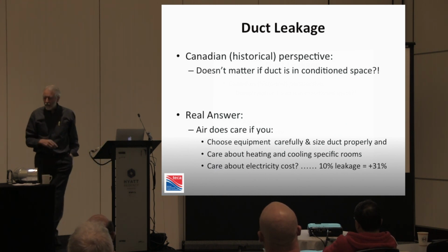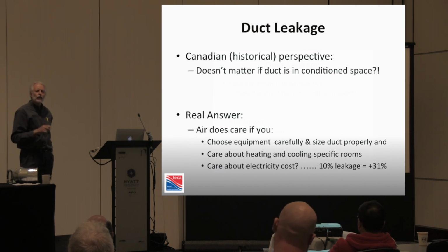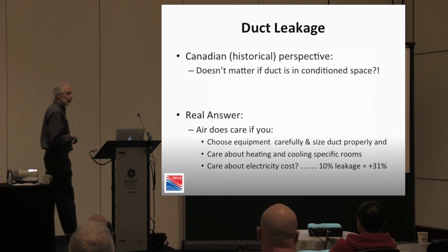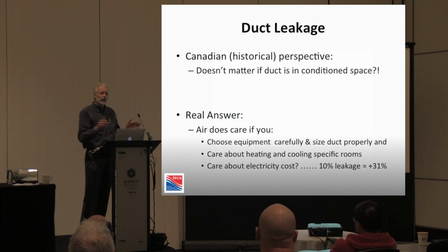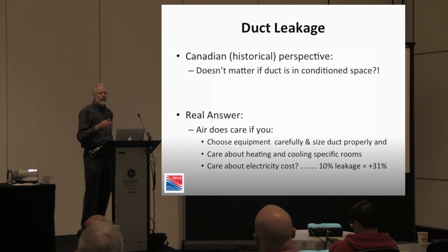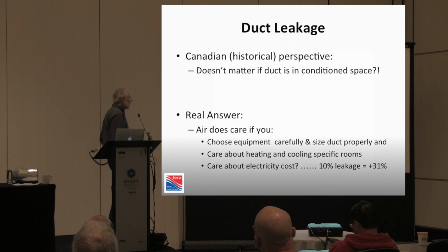Unfortunately, the Canadian perspective is ductwork doesn't matter because we traditionally kept our duct in conditioned space. That's the Canadian answer, and that comes from the National Research Council, and the code has never done anything about this, although just laterally 936 has touched on it, but it's a pretty weak issue. The real answer is air does care. As soon as you start choosing equipment and sizing the duct properly, you better start looking at leakage, or you're going to end up with Mrs. Smith not getting sufficient conditioned air to the bedroom.